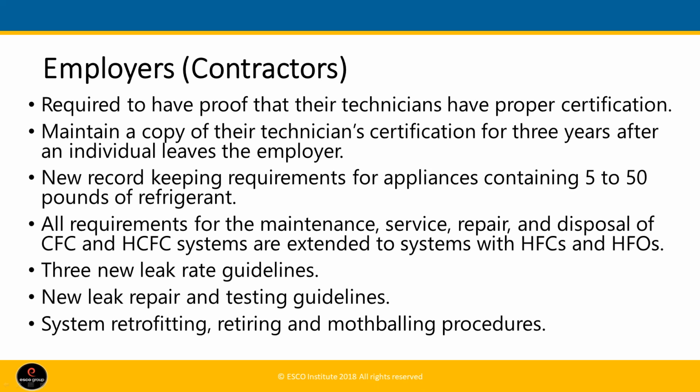Also, new record keeping requirements, as I said, for appliances containing 5 to 50 pounds of refrigerant become effective January 1st this year. All requirements for the maintenance, service, repair, and disposal of equipment containing Class 1, Class 2 substances are extended to the HFCs and HFO refrigerants.